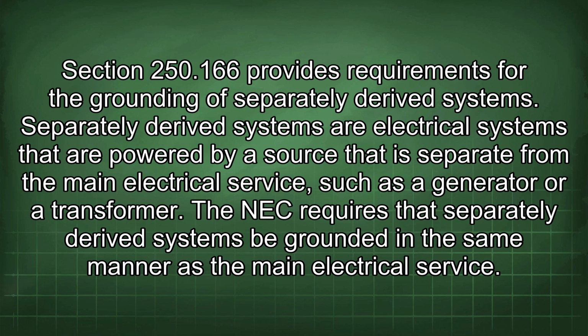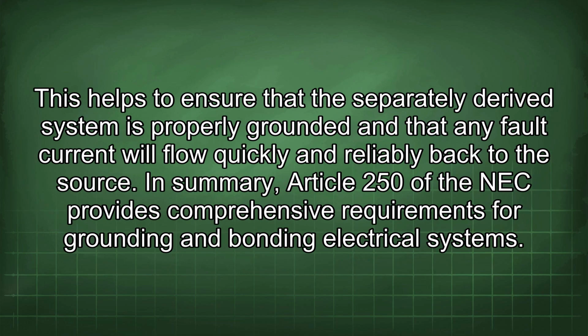Section 250.166 provides requirements for the grounding of separately derived systems. Separately derived systems are electrical systems that are powered by a source that is separate from the main electrical service, such as a generator or a transformer. The NEC requires that separately derived systems be grounded in the same manner as the main electrical service. This helps to ensure that the separately derived system is properly grounded and that any fault current will flow quickly and reliably back to the source.